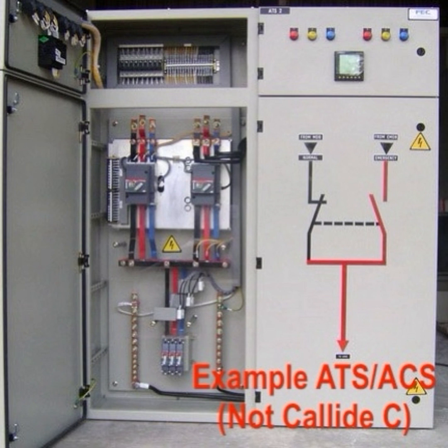74 seconds prior to the interconnector opening, when both chargers were operating in parallel, the Unit C4 charger was not outputting any current. Hence, when the interconnector was opened, the DC Unit C4 main bus went effectively dead. One wonders why the command to open the interconnector was given, seeing as how the charger wasn't outputting any current and the Unit C4 battery was still isolated. Maybe that'll become clearer in time in a future report.